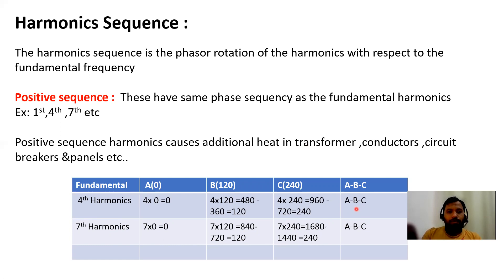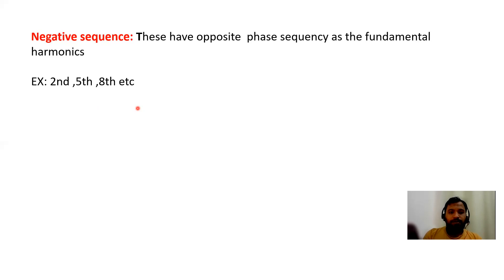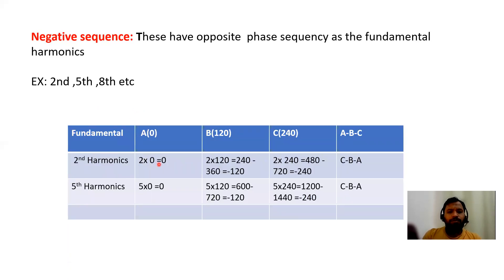Negative sequence harmonics are opposite to the fundamental phase sequence. Examples are the 2nd, 5th, and 8th harmonics. For the 2nd harmonic: 2×0=0, 2×120=240, and 240−360=−120. Then 2×240=480, and 480−720=−240. So the phase rotation is 0, −120, −240 — opposite to our fundamental. Therefore these are called negative sequence harmonics.